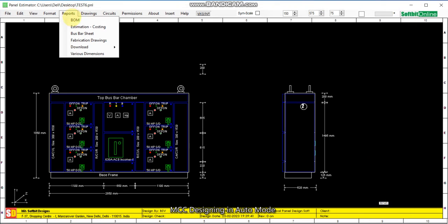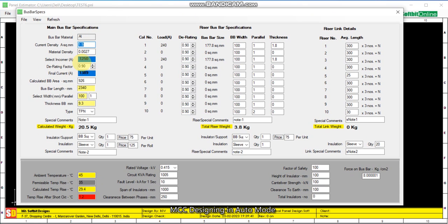Now we see the busbar calculations. This is the incomer selected automatically. The weight of the busbar is calculated. You can change the values as per your requirement and change the busbar material from aluminium to copper — accordingly the current density will change. These are the riser locations: riser number one, column number one — load is 240 amps; column number three — load is 240 amps. Total riser weight is 3.8 kg. The connecting links, temperature rise, and forces between busbars are also calculated.